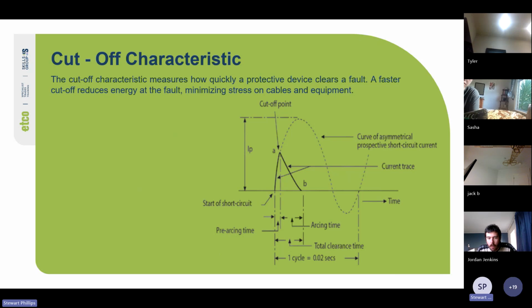So you've got your cutoff characteristic. The cutoff characteristic measures how quickly a protective device clears the fault. A faster cutoff reduces energy at the fault, minimizing stress on the cable. So you've got the start of the short circuit, the pre-arcing time, before the arc. Then you've got the arcing time once it starts to disconnect. And then the total clearance time is from the start of the short circuit to the finish of the arc. When we're talking about the arc, we're talking about the arc between the two ends of the circuit protection device. For example, with an HRC fuse, it's the amount of time it takes for the short circuit to start, then that silver strip to break, and then the silver oxide to form and quench the arc, or how long it takes that arc to travel up into the arc chute of a circuit breaker.